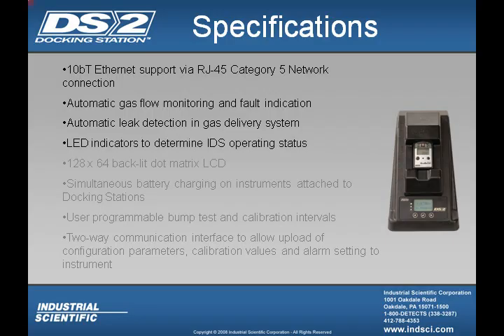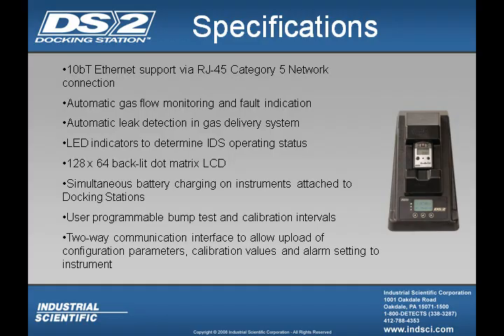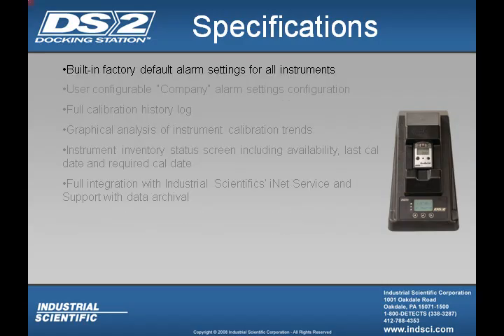You have LED indicators on the front of your IDS to give you operating status, as well as a display, which is a liquid crystal display 128 by 64. And you can also simultaneously charge batteries that are attached to your docking stations, as well as have user programmable bump tests and calibration intervals. And you also have a two-way communication interface to allow upload of configuration parameters, calibration values, and alarm settings to the instrument. And the docking station will provide built-in factory default alarm settings for all instruments, as well as a user configurable company alarm setting configuration.